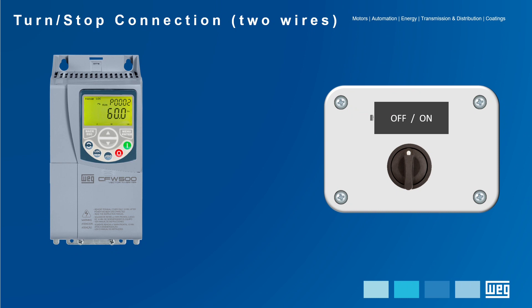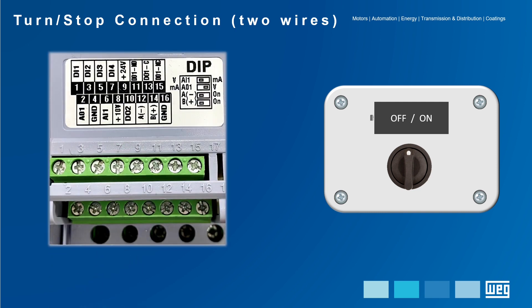In the TURN STOP command, also called ON OFF or two-wire control, it is recommended to use a normally open contact block associated with a fixed selector switch connected to the digital input of the plugin module. It is worth remembering that for this example we will consider the CFW500 IOS standard plugin module as the basis. For other plugin modules, the user must pay attention to the identification of the terminals related to the chosen model.